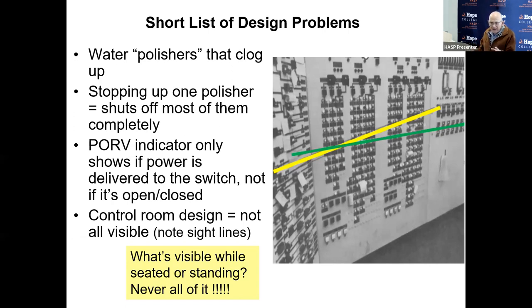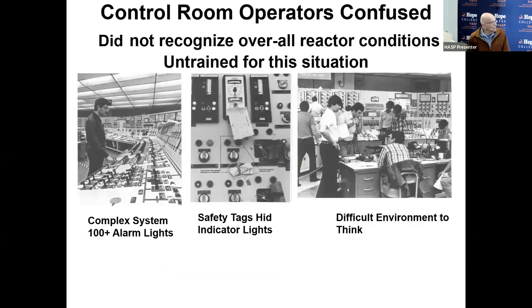That next day, when it's daylight and the other shift comes on, a different operator stands by each panel of the control room so that they can verbally yell to each other what they're seeing, because the operator can't see everything. Complex system, 100 alarms. Oh, maintenance tags, safety tags, hid some indicator lights. Difficult environment in which to think.